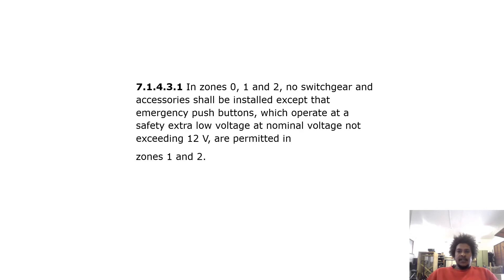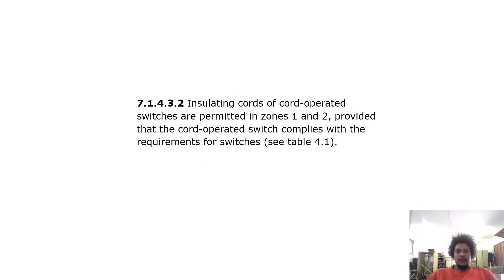Switchgear and control gear in zones 0, 1 and 2: no switchgear or accessories shall be installed, except that emergency push buttons which operate at SELV at a nominal voltage not exceeding 12 volts are permitted in zones 1 and 2. Insulating cords of cord-operated switches are also permitted in zones 1 and 2, provided that the cord-operated switch complies with requirements for switches — see Table 4.1.